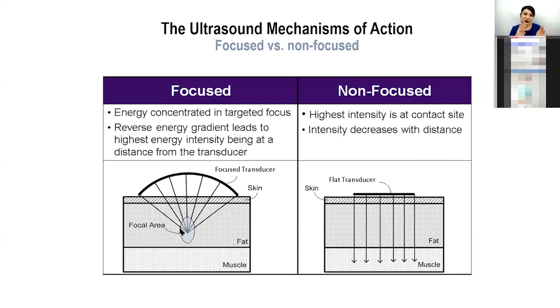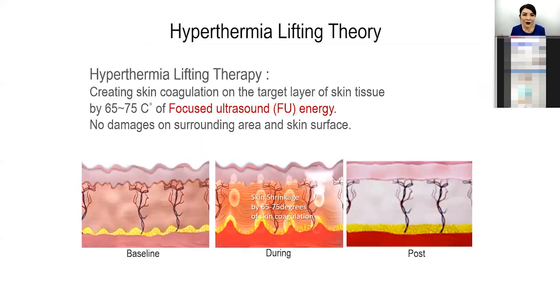That is why we have different transducers to target different depths from the skin: 1.5, 3.0, and 4.5. So that is how we can use the focus transducer to deliver the energy to the target. Why are we talking about all the energy? Because we want to make sure that the energy and the temperature are high enough to cause the lifting, because all we need is the lifting. Which means what you need is to deliver to the target tissue 60 to 70 degrees Celsius.